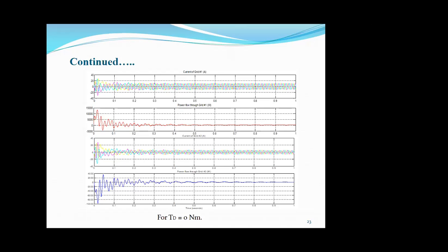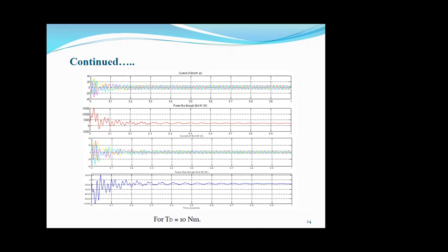Now, if I increase the magnitude of torque TD from 0 Newton meter to 10 Newton meter, you will see grid 1 power becomes positive, around 2 kilowatt, and grid 2 power becomes negative. This means grid 1 is supplying power to grid 2 through the VFT. Also, the current waveforms are stable.